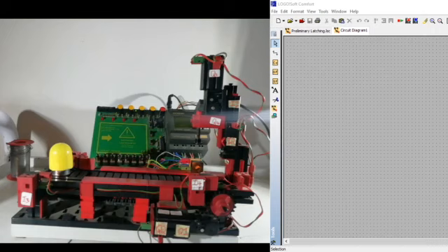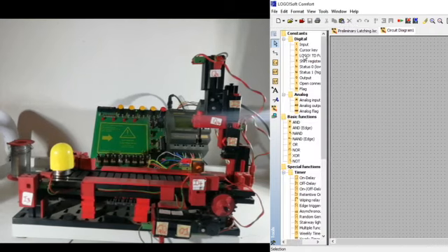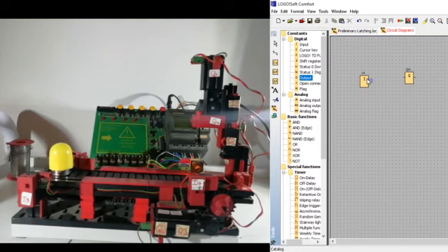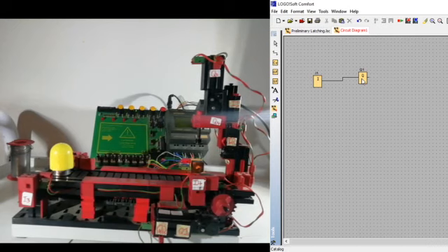One thing I need to be careful of is whether that input is normally closed or currently pressed, because if it is currently pressed, the machine is bound to move in an opposite direction, or it would execute an unintended process.